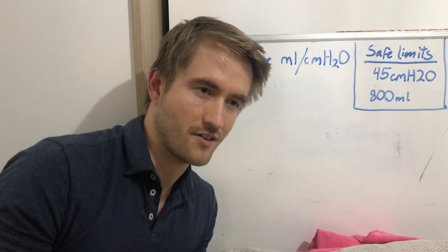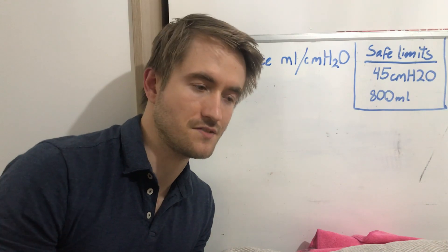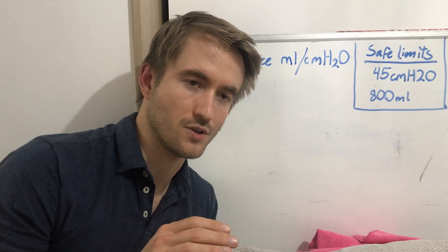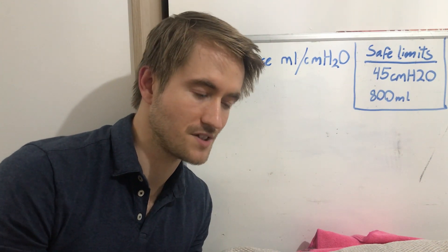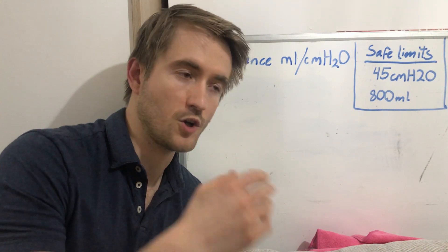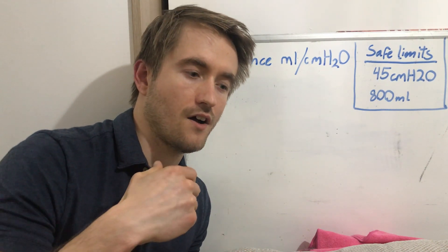But that's not necessarily a bad thing, and I'll explain. Under those more extreme levels where compliance is very low and resistance is very high, as per the numbers in the table in the requirements document, if a ventilator successfully ran those tests, it would actually produce an unsafe pressure level in order to do so. They're asking for 500 millilitres of breath to be achieved with quite low lung compliance, which means a very high pressure.